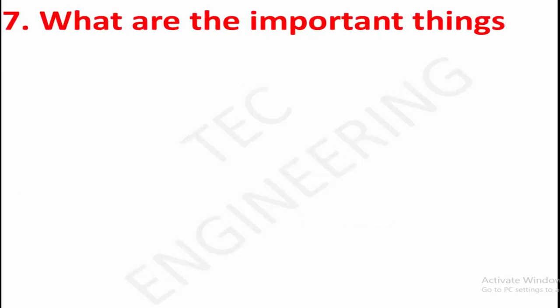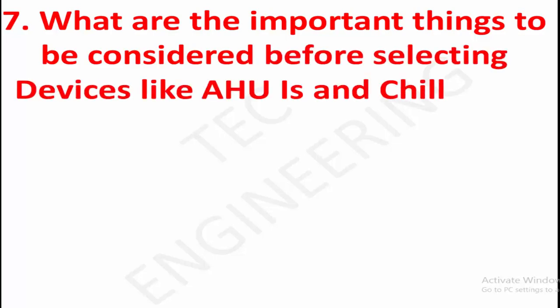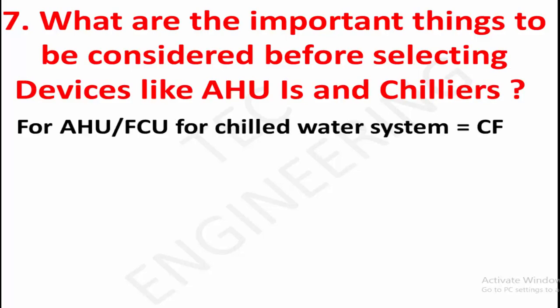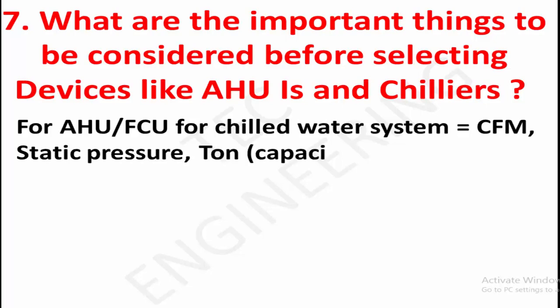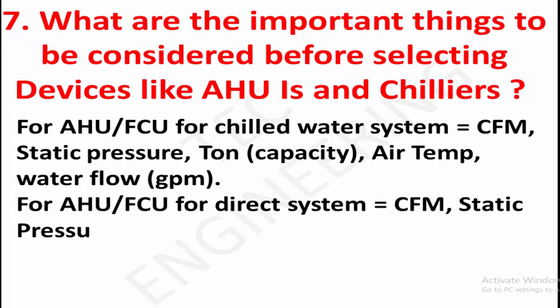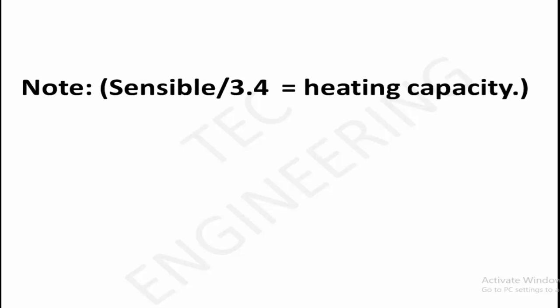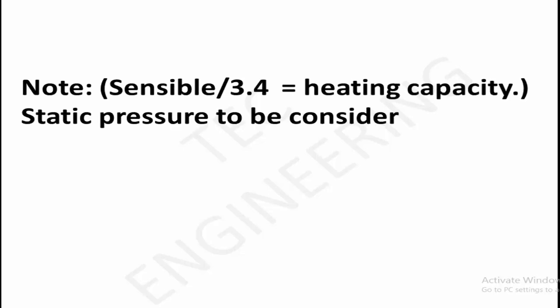What are the important things to consider before selecting devices like AHU and chillers? For AHU/FCU in a chilled water system: CFM, static pressure, ton capacity, air temperature, water flow, and GPM. For AHU/FCU in a direct system: CFM, static pressure, and ton sensible. For chillers: ton, outside air temperature, and GPM. Note: sensible divided by 3.4 equals heating capacity. Static pressure must be considered for fan selection.